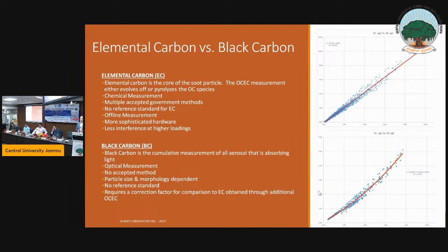So if you have a filter that has a high amount of any metal oxide, I usually use iron oxide because everybody knows rust. If you have iron oxide on your filter, you have a source of oxygen. That oxygen is tightly bound in a chemical bond between iron and oxygen. But as we all know from our physical chemistry classes, you give anything enough heat and something's going to happen. Our instruments get really hot, 700, 800, 900 Celsius, and I can't think of an example that doesn't provide oxygen as a source of oxidation at that high temperature, but especially rust.